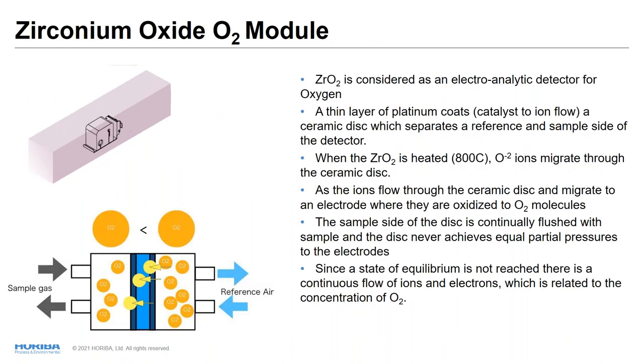Zirconium oxide O2 modules are another way to measure oxygen. Zirconia O2 is considered another electroanalytic detector for oxygen. A thin layer of platinum, you can see here, coats a ceramic disc, this blue one. When the zirconia O2 is heated to 800 degrees C, oxygen ions migrate through the ceramic disc, so ions flow through the ceramic disc from higher O2 concentration to lower concentration.